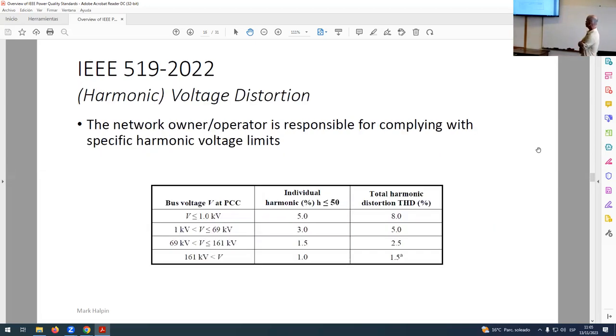The voltage distortion, again, this is a standard table that we have. The only relatively new thing here is the addition of another row. We traditionally had three rows in this table. These two were combined together. So anything less than 69 kV, you had a maximum individual harmonic of 3%.